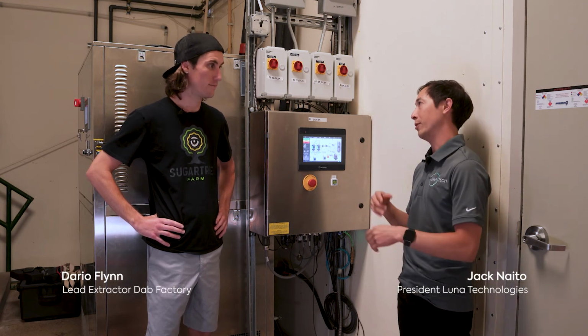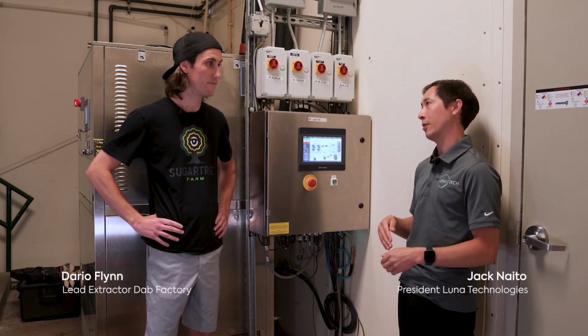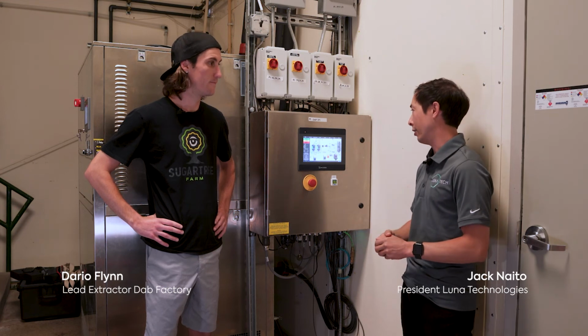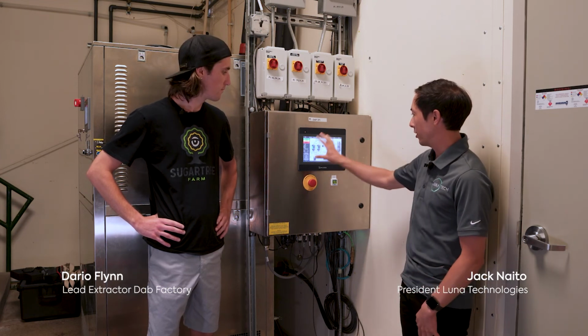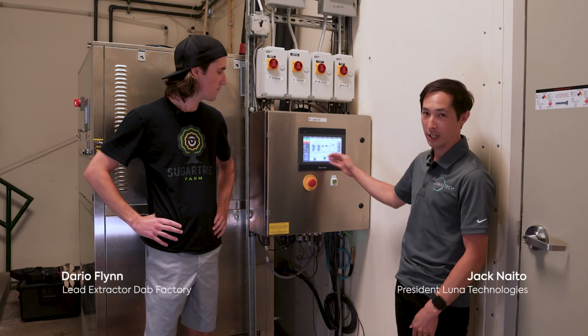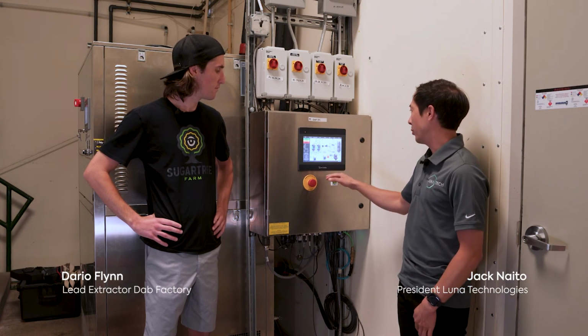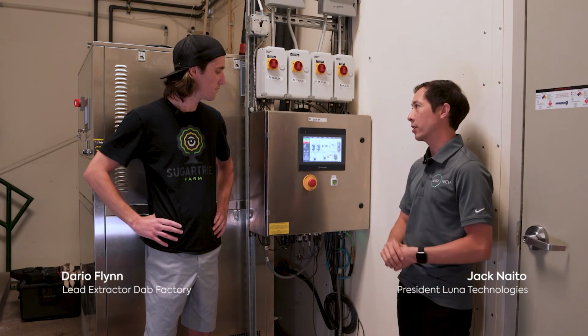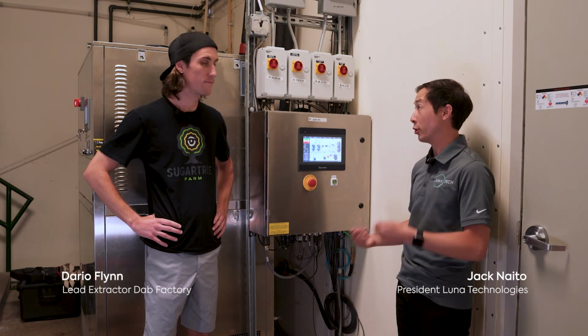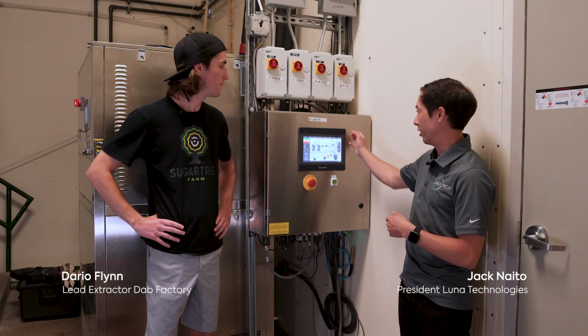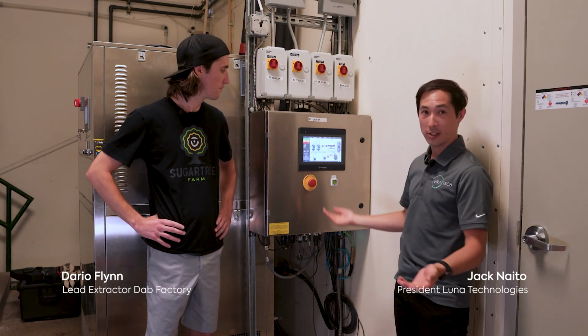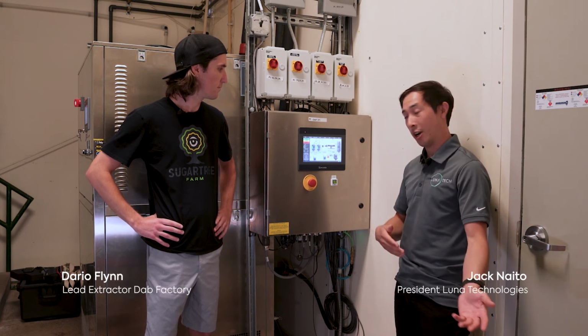You can maybe spot a leak, or spot if something's out of whack and you need to check it out. We also have all of our auxiliary systems here, so all our chillers, heaters, and pumps. And we also have manual control, so if something does get out of whack and you have to do troubleshooting, you can do it from out here. You can just click a valve and override the status, either flip it to on or off.